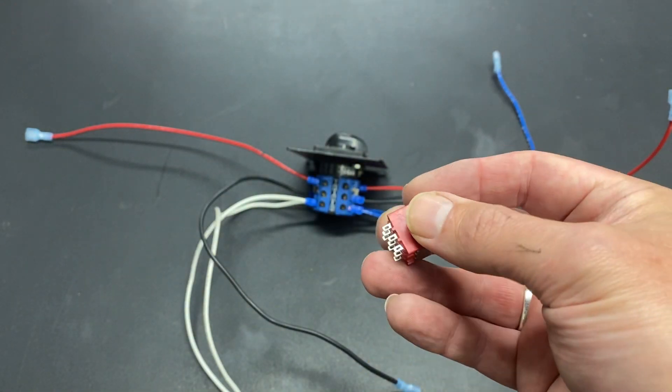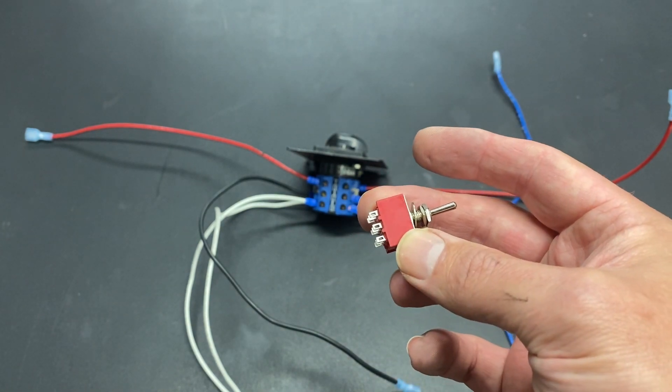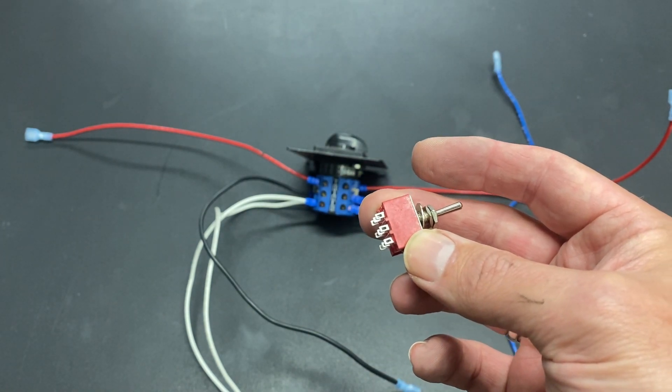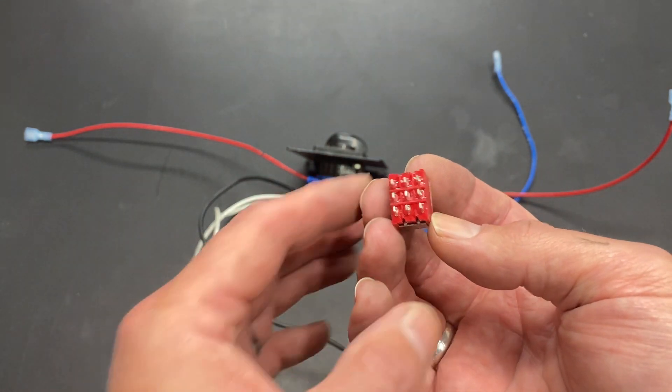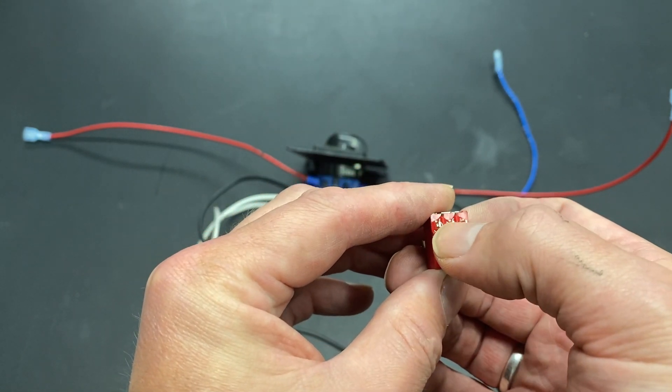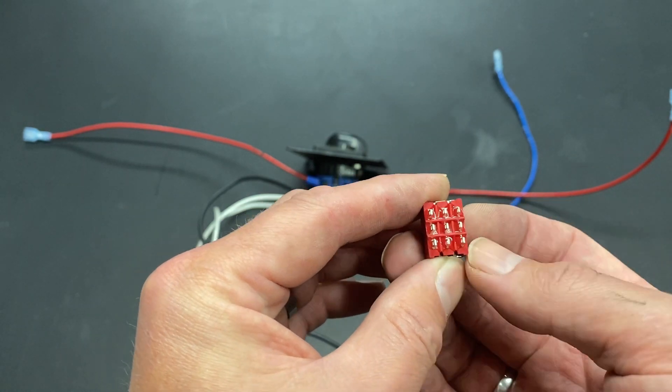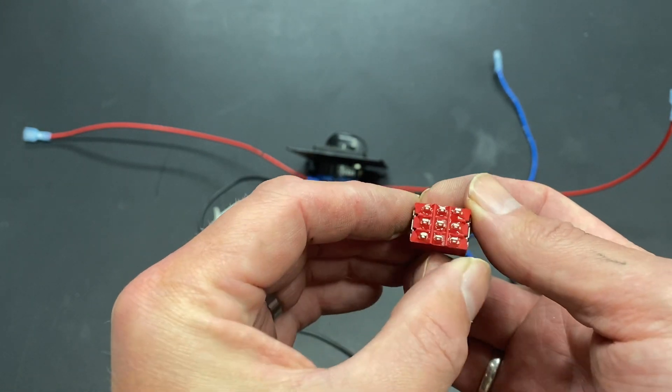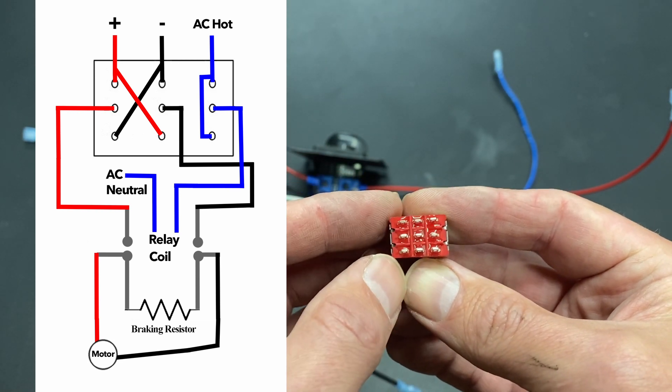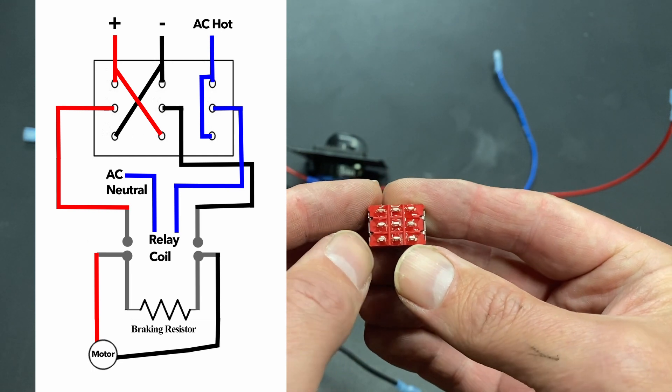So this is a triple pole double throw switch. Now this is way too small for this application but the good news is this is configured the exact same way that a switch that is large enough for this application would be. The center terminals are the ones being switched and they're either being switched to this side or this side up the row. So we wire this just the way we would with a double pole double throw switch using these six terminals to control the forward and reverse direction and using these three terminals to turn off and on the AC that goes to the coil.